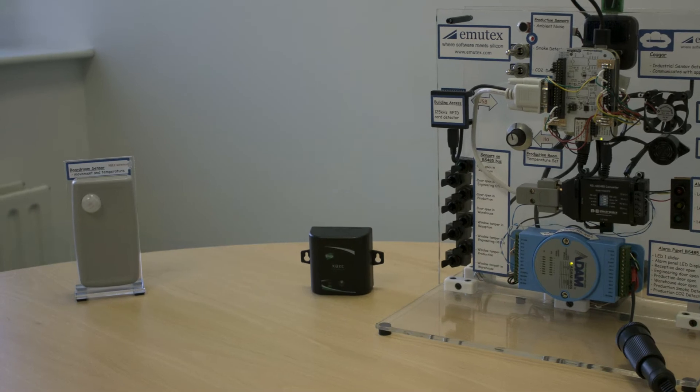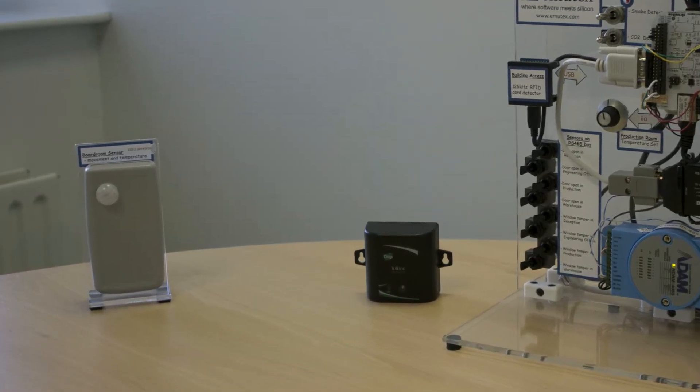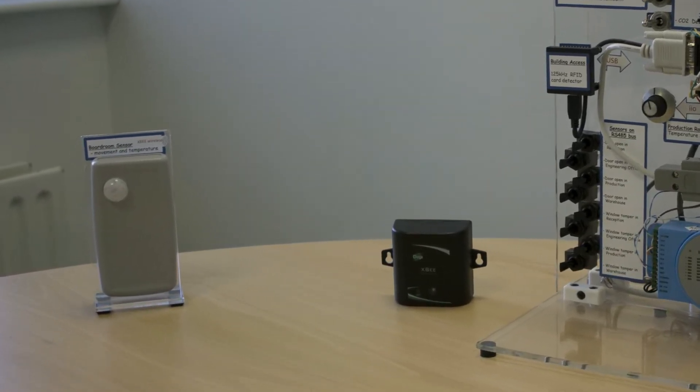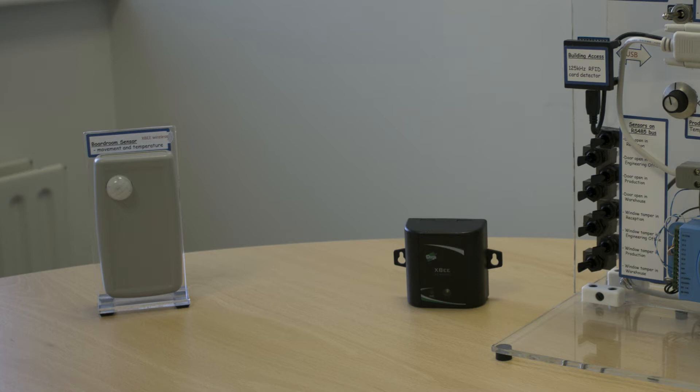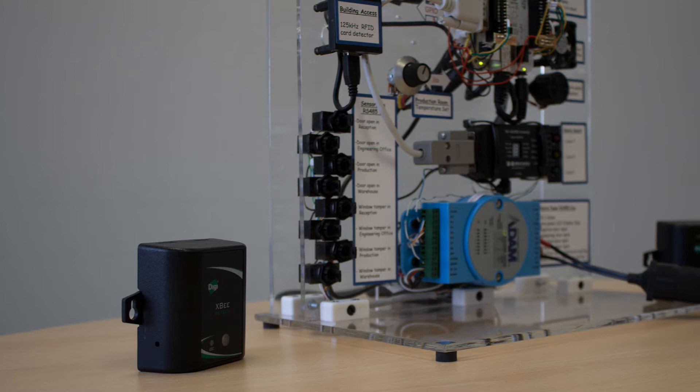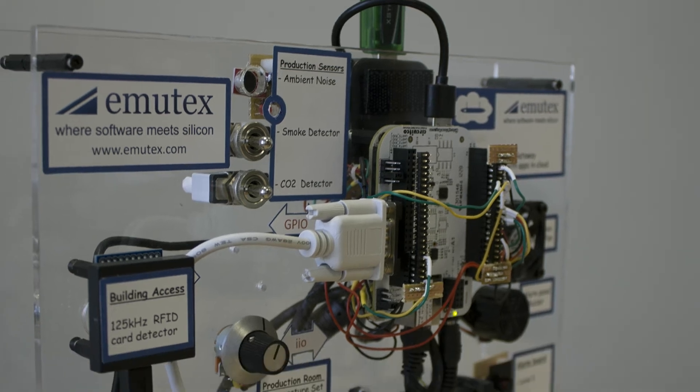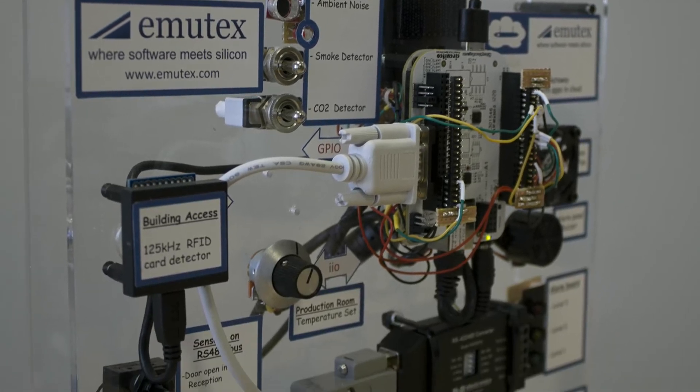For proximity or movement detection we have four remote passive infrared motion detectors communicating via wireless XBee to the board. These transmit readings once a second to the sensor gateway. Two additional wireless XBee sensors communicate light level, humidity and temperature. An analog input IIO connected noise detector allows us to remotely monitor for loud noises or events.